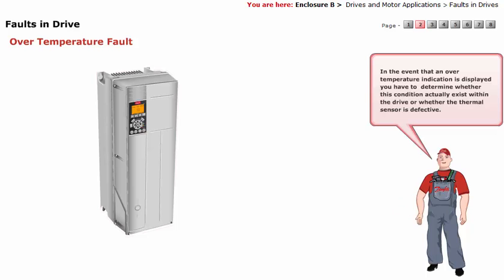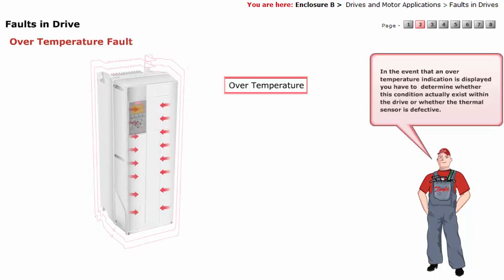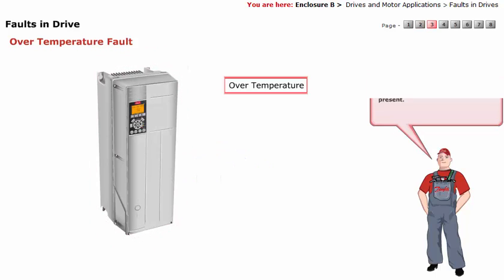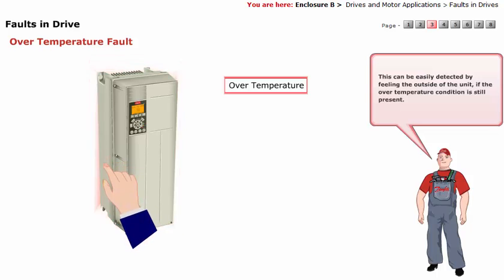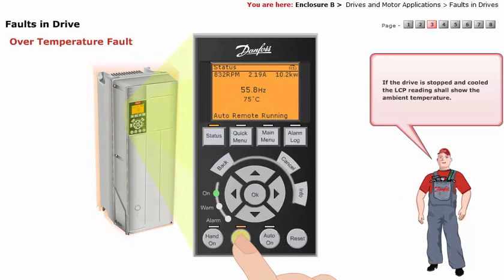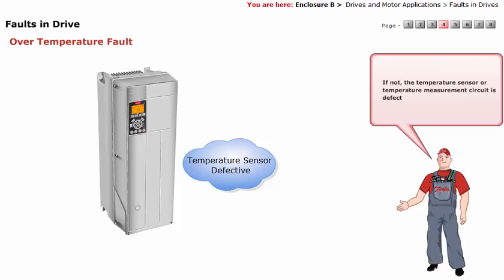In the event that an over temperature indication is displayed, you have to determine whether this condition actually exists within the drive or whether the thermal sensor is defective. This can be easily detected by feeling the outside of the unit if the over temperature condition is still present. If the drive is stopped and cooled, the LCP reading shall show the ambient temperature. If not, the temperature sensor or temperature measurement circuit is defective.